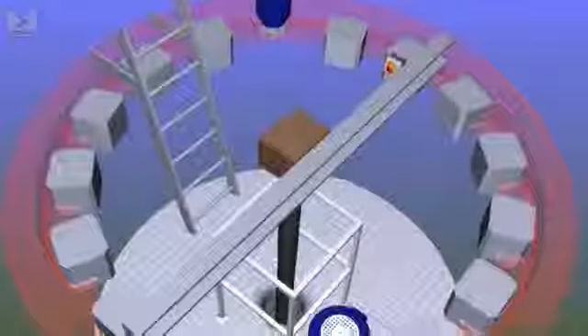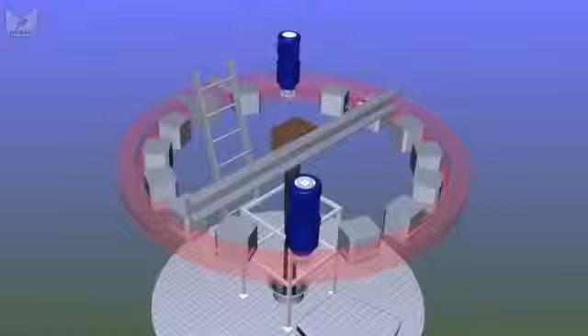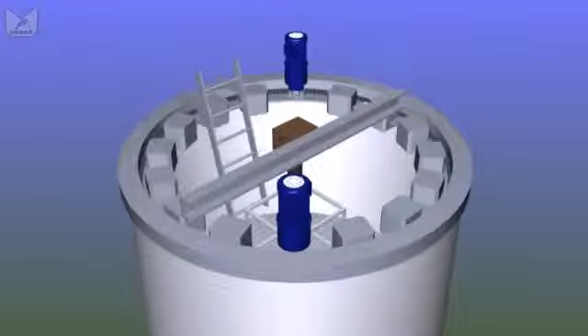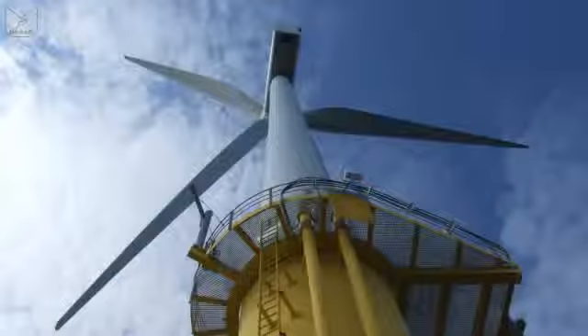Series of disc brakes run around that yaw ring to lock it in position when the wind isn't changing direction. And when it is, we have a series of either electric or hydraulic motors that rotate the entire mechanism around on the top of the tower. The layout of a multi-megawatt nacelle is, again, more variable than for a smaller version.